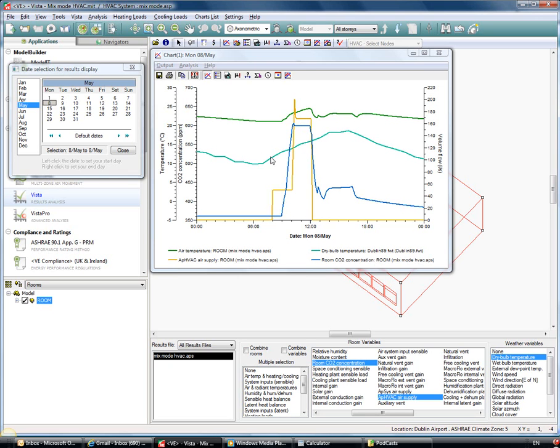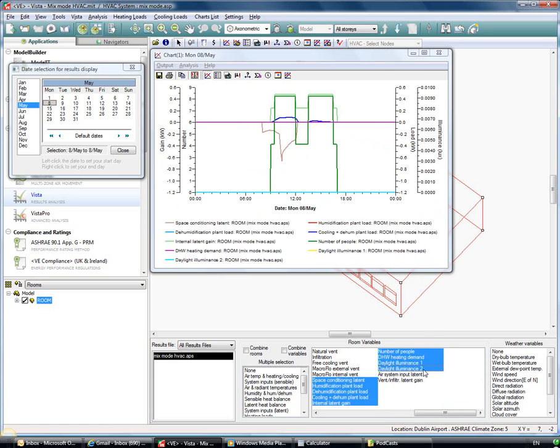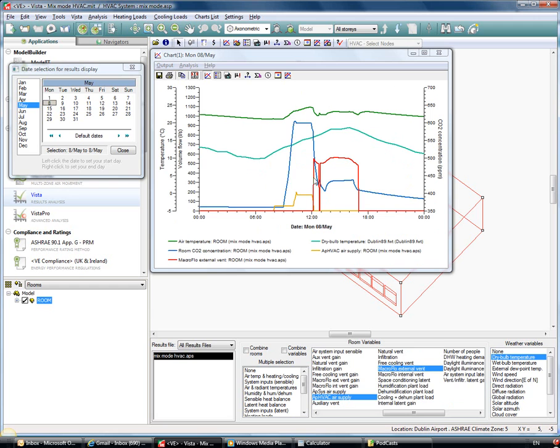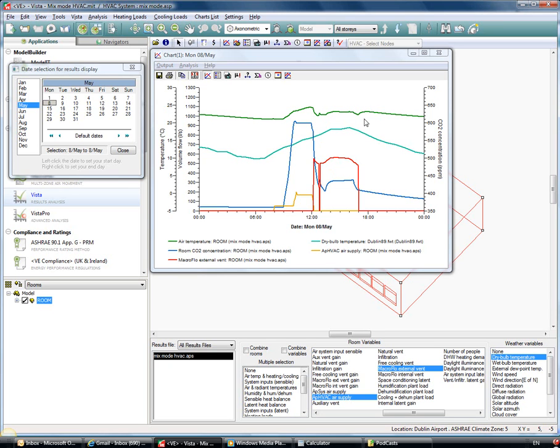Once the temperature outside goes above 16 degrees C and the air temperature inside is above 22, then our natural ventilation will come on. And so you can see that macro flow external vent coming on there, so our macro flow is coming on in that afternoon period where the temperature in the space is above 22 and it's keeping the temperature in the space within our comfort limits.